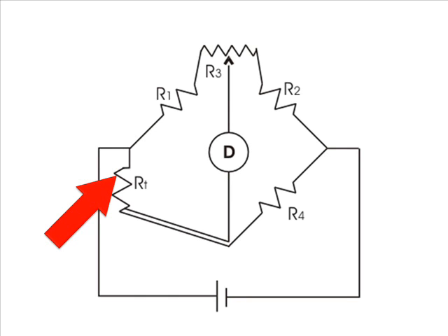This drawback can be eliminated by using three wire RTD. Here the RTD bulb is connected as one arm of the bridge as shown. The third wire is connected to the sliding contact of variable resistance R3 via a galvanometer as shown.